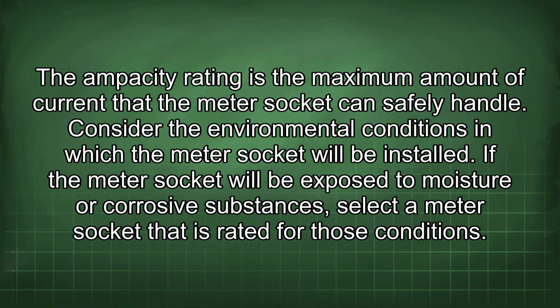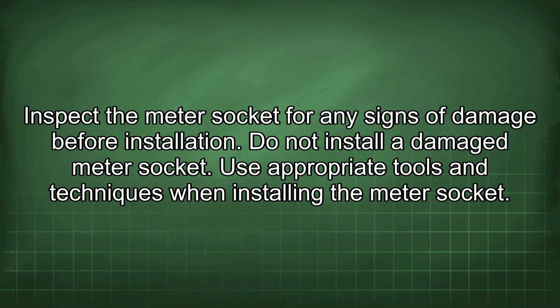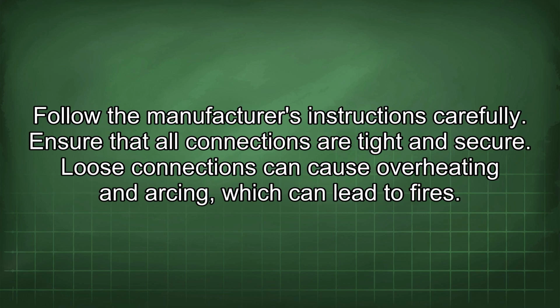Consider the environmental conditions in which the meter socket will be installed. If the meter socket will be exposed to moisture or corrosive substances, select a meter socket that is rated for those conditions. Inspect the meter socket for any signs of damage before installation. Do not install a damaged meter socket. Use appropriate tools and techniques when installing the meter socket. Follow the manufacturer's instructions carefully. Ensure that all connections are tight and secure. Loose connections can cause overheating and arcing, which can lead to fires.